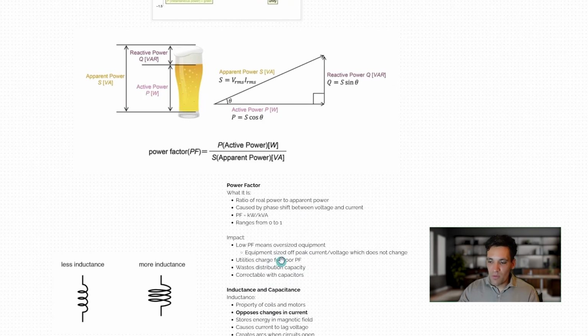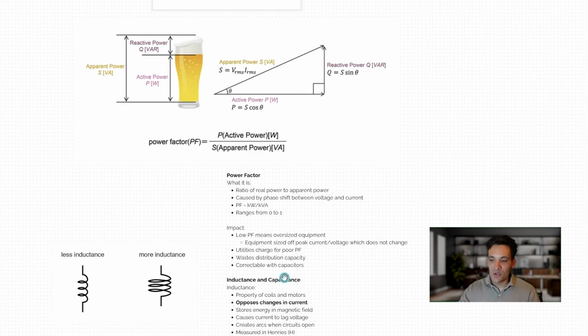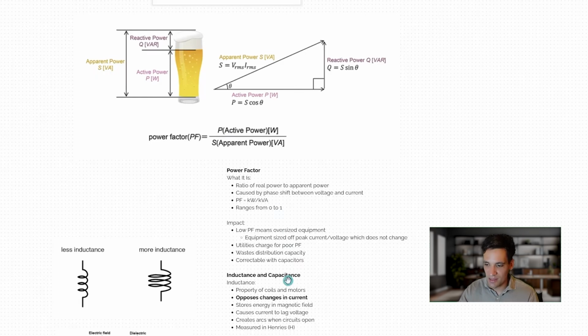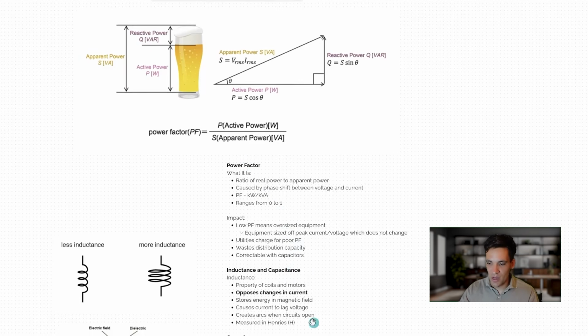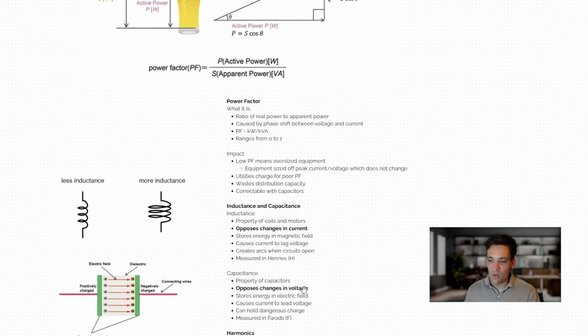So low power factor means that we've still got to size the system. The size of the cables and the size of the generators is all based on the apparent power, but we're only transmitting useful active power. So low power factor is bad. We want a number as close to 1 as possible because it reduces waste in the system. The reason you don't always have a power factor of 1 is because of inductance and capacitance in circuits.